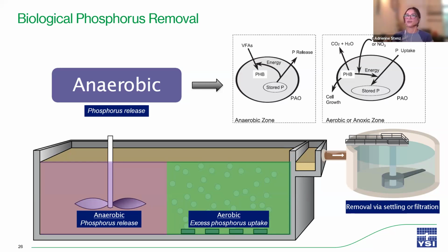Anaerobic zones accumulate what are called PAOs, or phosphorus accumulating organisms. These PAOs are grown in the anaerobic zone, and then once they enter an aerobic zone downstream, they uptake all of the phosphorus out of the water. Anaerobic zones are zero oxygen environments, so they are typically at the front of a treatment train with a mixer there to keep bugs suspended.